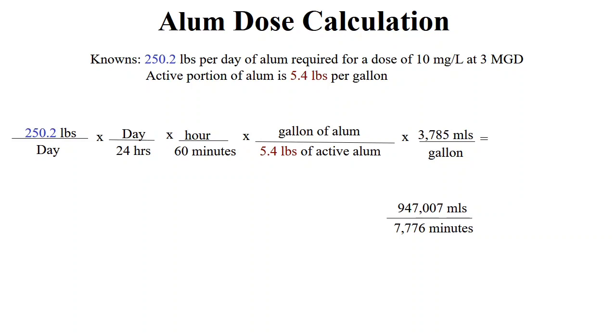Now it's just a matter of canceling units. Pounds in the numerator cancel with pounds in the denominator; days, hours, and gallons all cancel out, leaving us with milliliters per minute. Multiplying 250 times 3,785 gives 947,007 in the numerator. Multiplying 24 times 60 times 5.4 gives 7,776 in the denominator, which equals 122 mL per minute of alum.